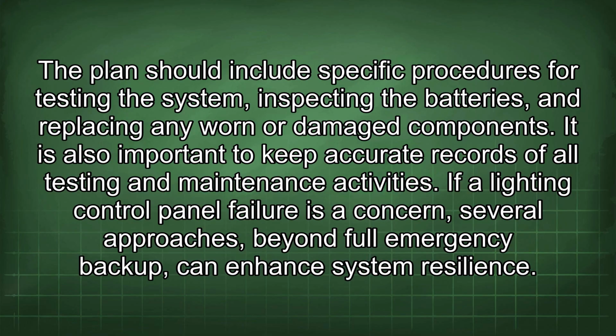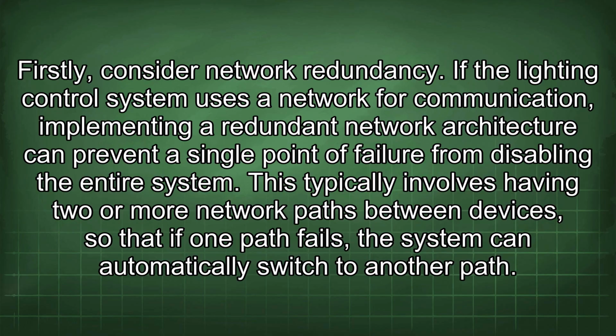If a lighting control panel failure is a concern, several approaches beyond full emergency backup can enhance system resilience. Firstly, consider network redundancy. If the lighting control system uses a network for communication, implementing a redundant network architecture can prevent a single point of failure from disabling the entire system. This typically involves having two or more network paths between devices, so that if one path fails, the system can automatically switch to another path.